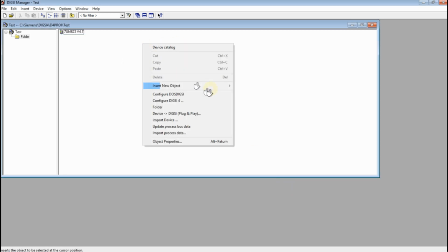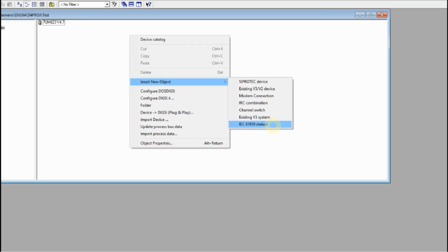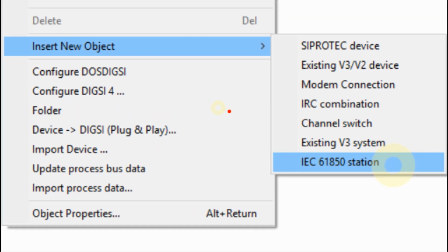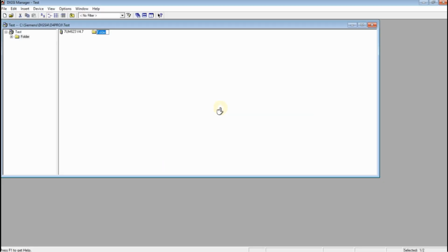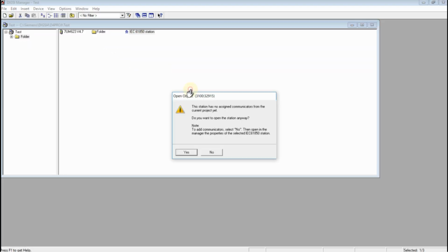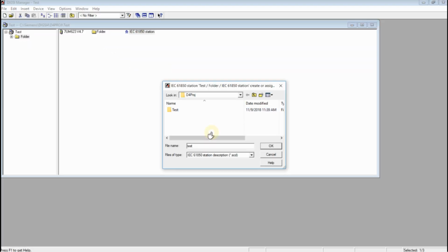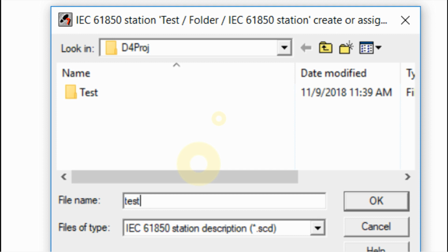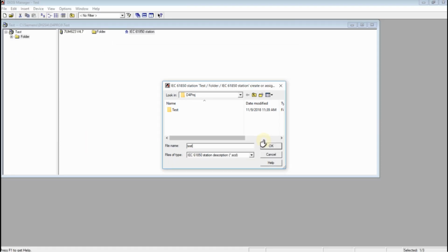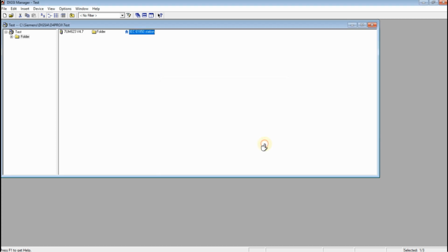Now to confirm that 61850 is correctly functioning, you must create an IEC 61850 station in this project. Click insert new object and 61850. Double click to open. Yes, just put the station description file anywhere that you locate the project. For example, in this test project, I also put the name test.